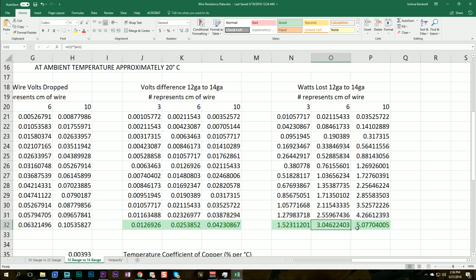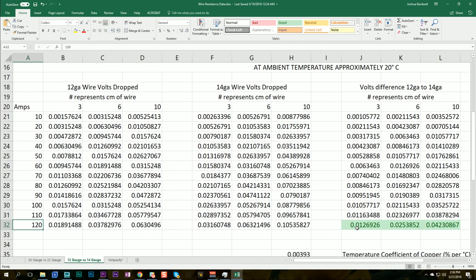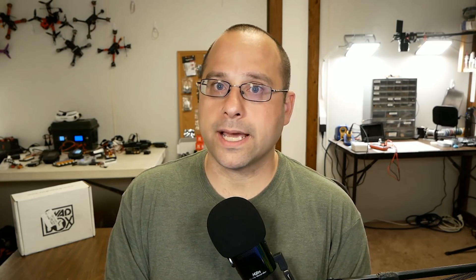And remember that that is at 120 amps. At lower numbers, it's even less. Another argument that some people made was that you can't just calculate the resistance at 50 amps and then scale that up and down to higher or lower values. They argued that there was a characteristic of the wire where the resistance would be non-linear. As the amps goes up, you'd actually see an increase in the measured resistance, the voltage drop, and so on. So they argued that my higher numbers were actually too conservative.